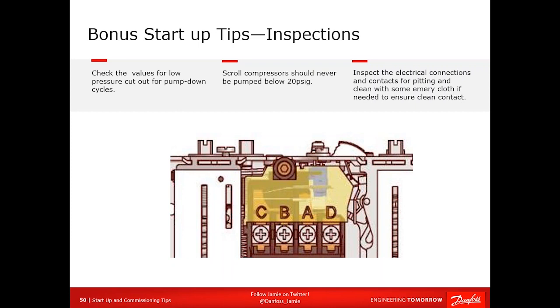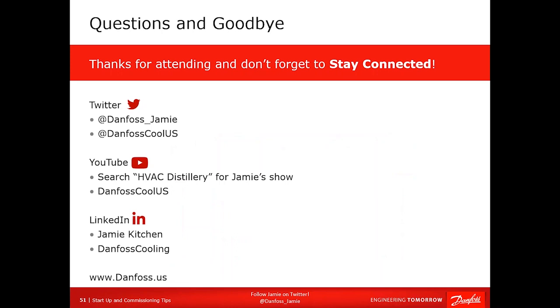Also, scroll compressors, never pump them into a vacuum. Make sure you set this thing at least 15 or 20 pounds or whatever the manufacturer recommends, even in refrigeration. Never, ever pump a scroll into a vacuum. I wouldn't pump a regular compressor into a vacuum anyways, but never pump a scroll into a vacuum. You will not get it back again.